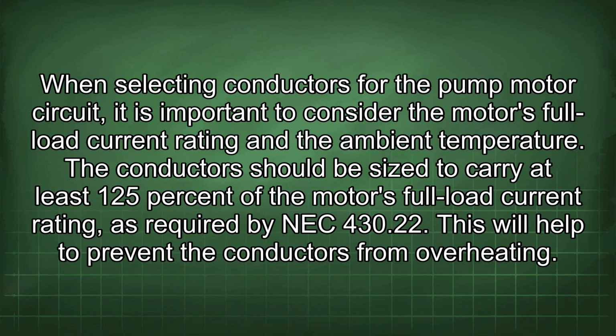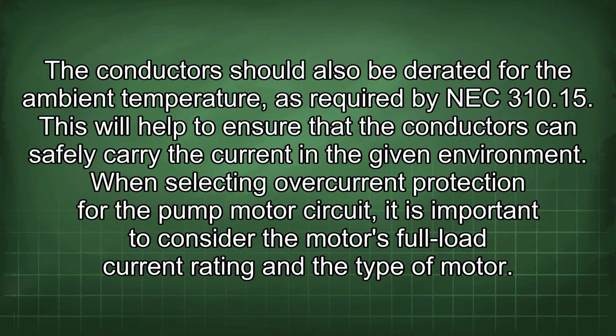When selecting conductors for the pump motor circuit, it is important to consider the motor's full load current rating and the ambient temperature. The conductors should be sized to carry at least 125% of the motor's full load current rating as required by NEC 430.22. This will help to prevent the conductors from overheating. The conductors should also be derated for the ambient temperature as required by NEC 310.15. This will help to ensure that the conductors can safely carry the current in the given environment.